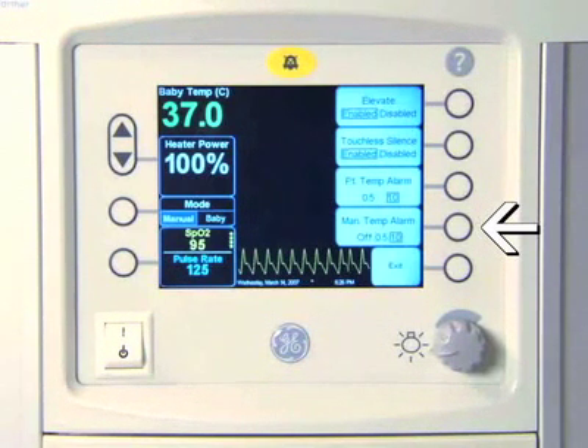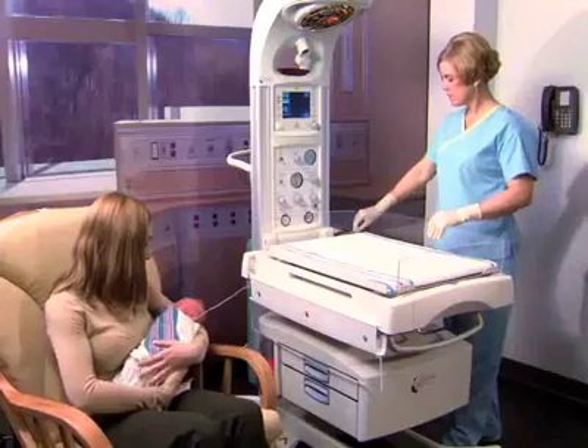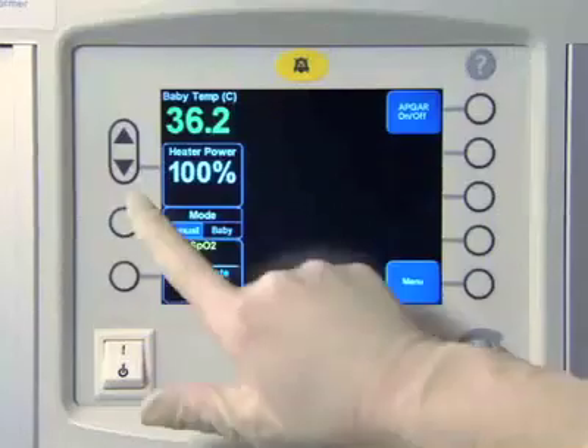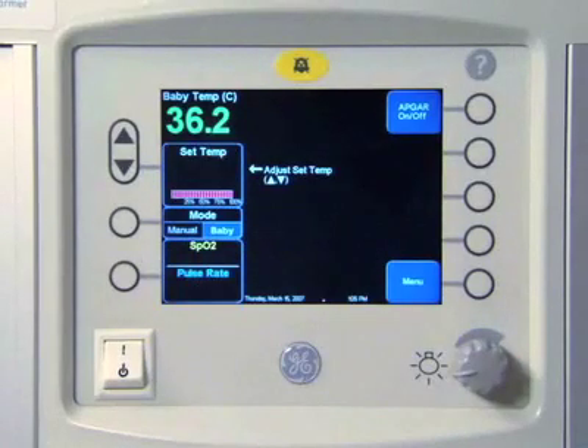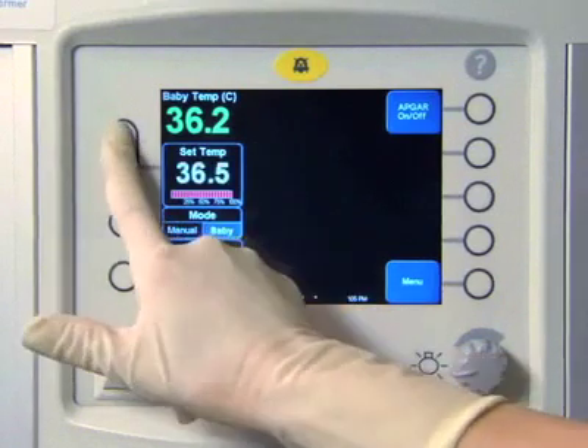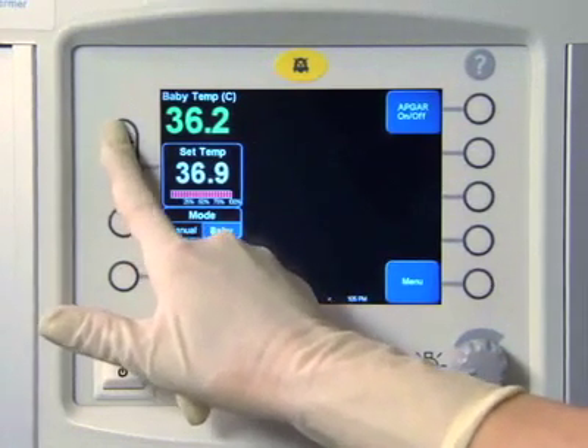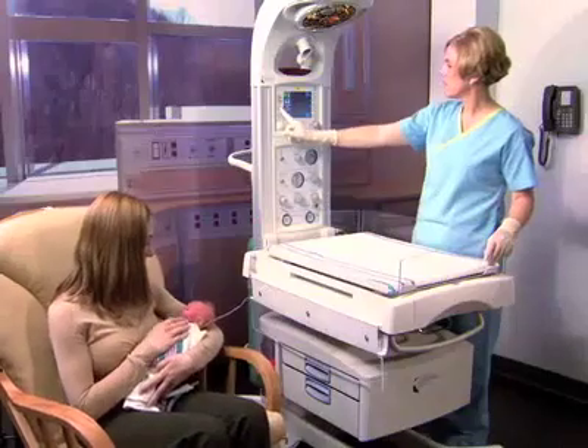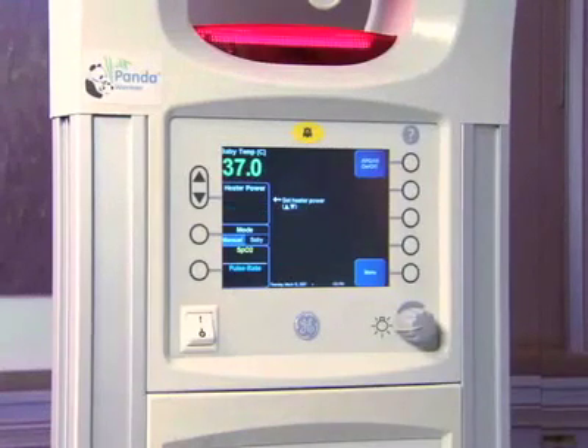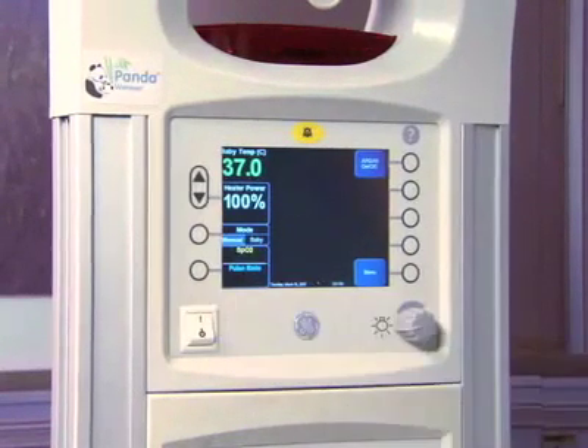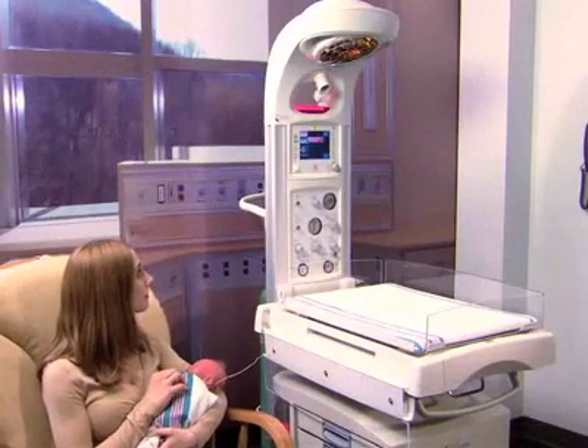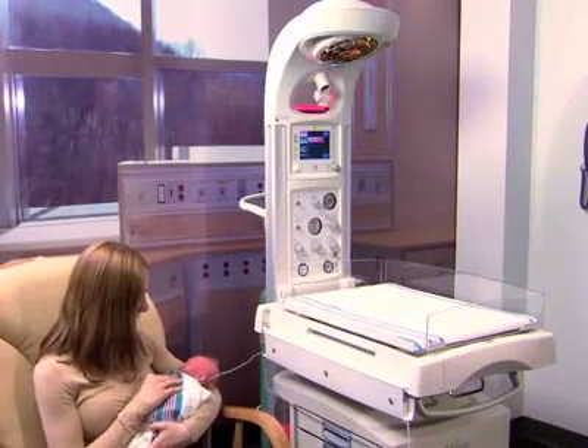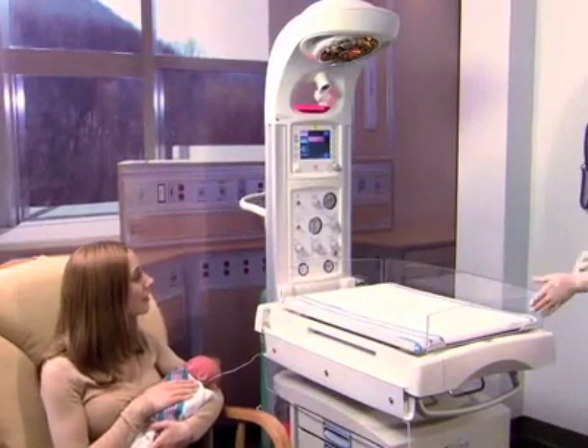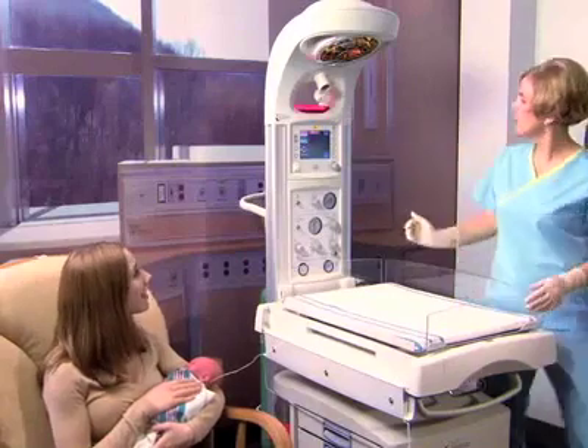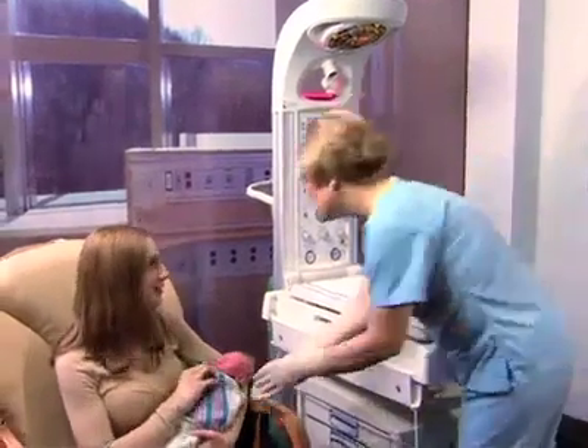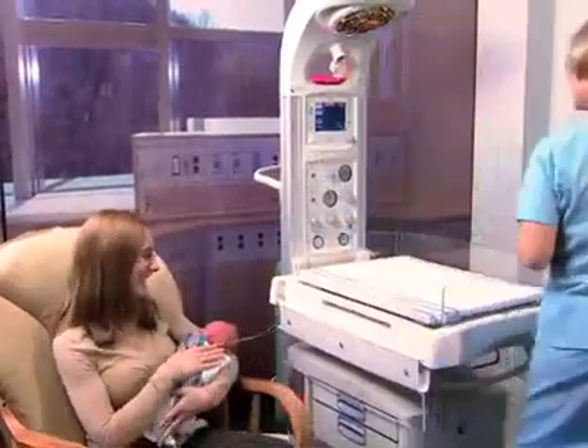Change the temperature control mode temporarily from manual mode to baby mode and enter a set temp. This will serve as your desired notification parameter. Return to manual mode. Confirm the heater power. When the baby's skin temperature exceeds the value you entered by greater than plus or minus 0.5 degrees Celsius or plus or minus 1 degree Celsius, you will receive a baby hot or baby cold alarm.